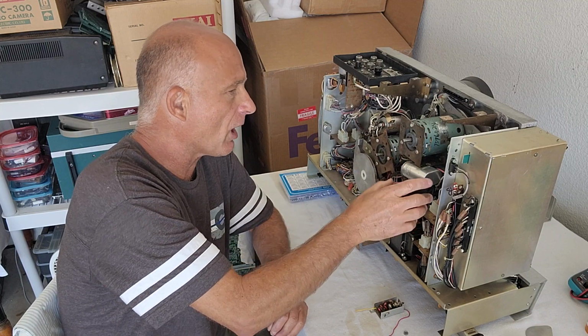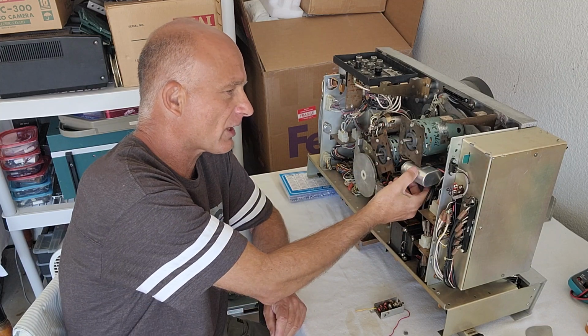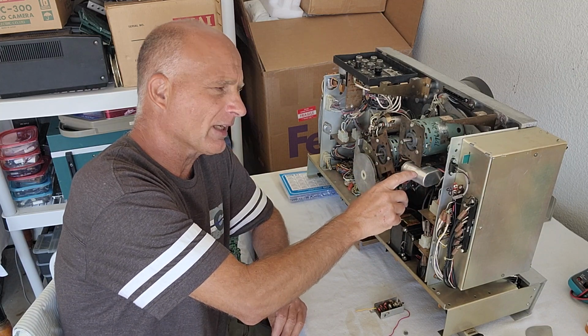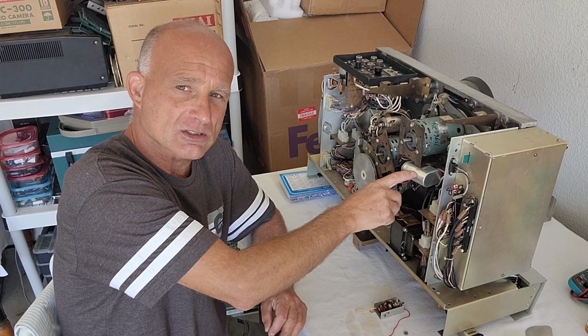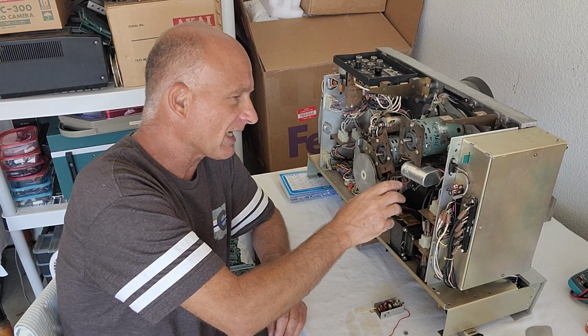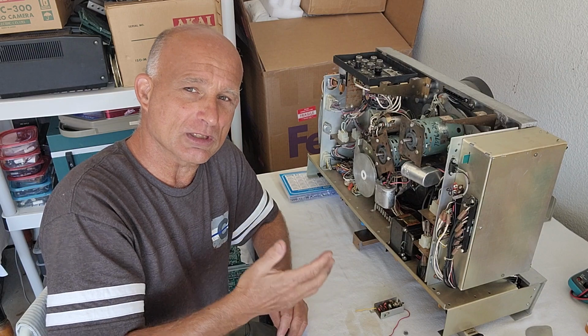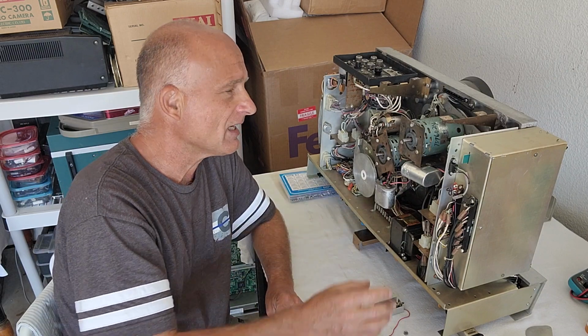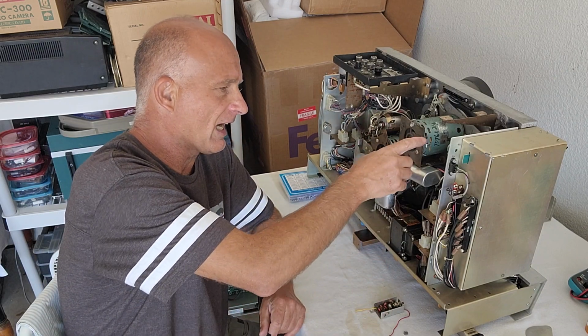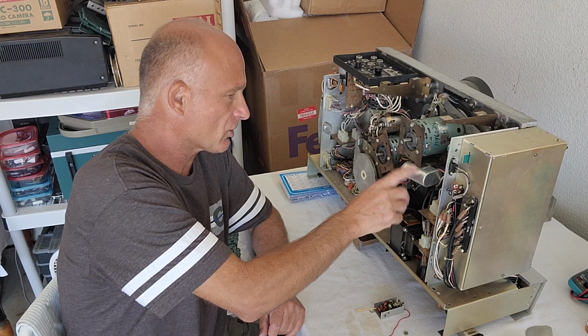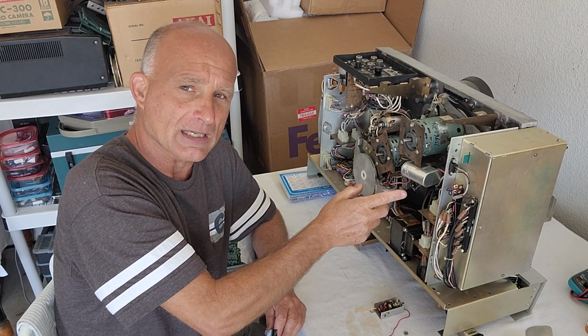So when I had this off and put the new belts in, I checked this cap, and this one here is way off the charts. That usually means if it's that high out of value, the capacitor is bad. So I'm not going to risk turning it on with this old one - we're going to change them all out to new capacitors.